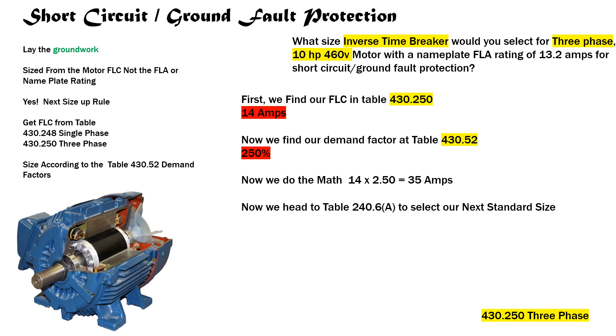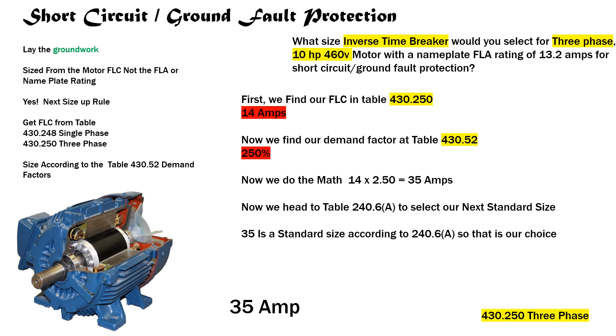We head to table 240.6(A) to select our next standard size. When we get there we find out that 35 is actually a standard size. That may not be one we use in the field very often, but when you're testing or if this were truly code-legal, that would be the size breaker or fuse you'd have to select. So our answer is 35 amps for short circuit ground fault protection.